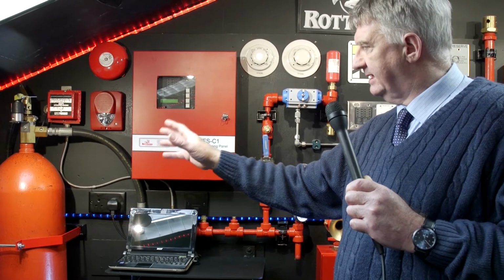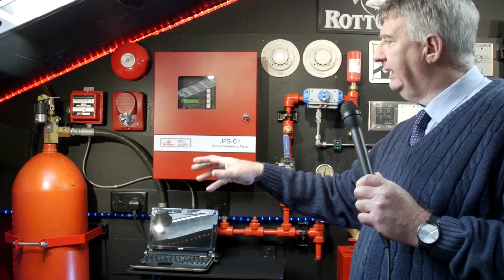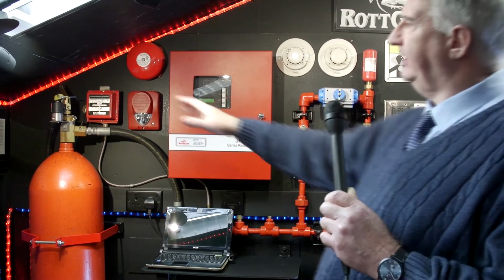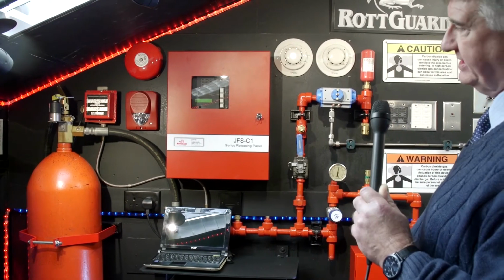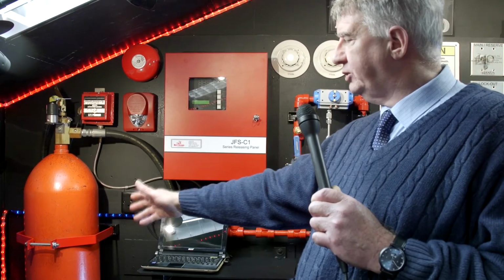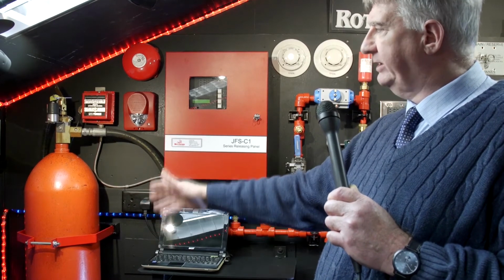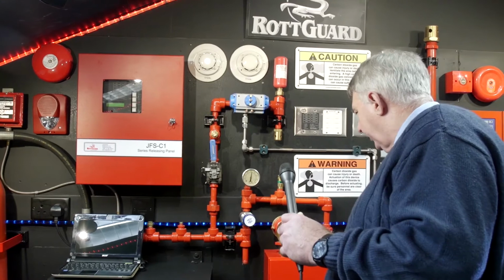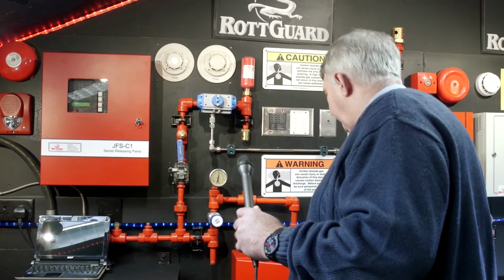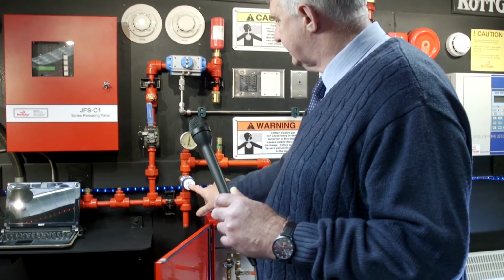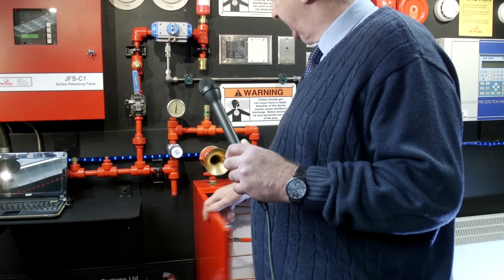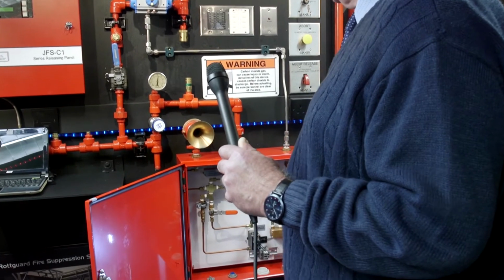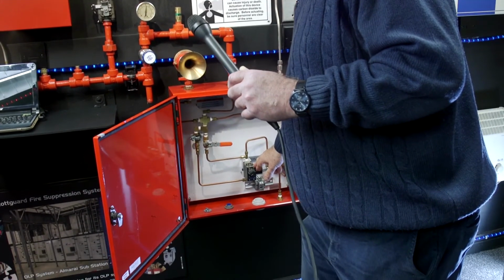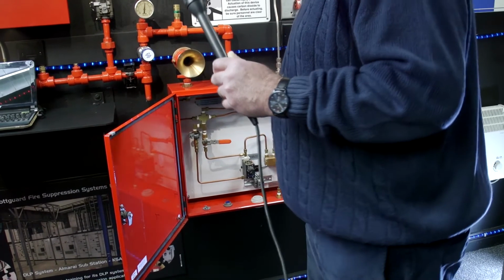The liquefied CO2 in this instance is stored at approximately 850 psi. It doesn't have any pressure gauge on it compared to the other system because the pressure of the CO2 within the cylinder will fluctuate with temperature throughout the day. The pilot control panel operates pneumatically in that this regulates the pressure down to 100 psi. That pressure is used to control a pneumatic timer in this instance, which can be set generally again to 30 seconds.